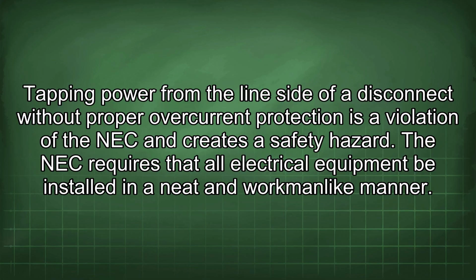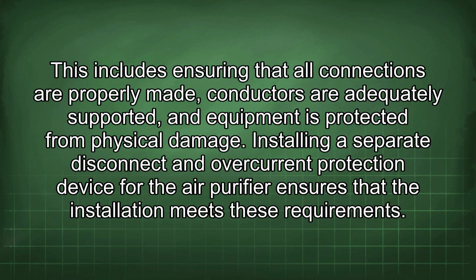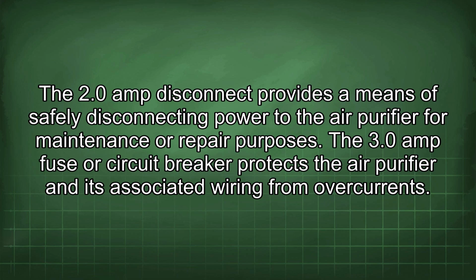The NEC requires that all electrical equipment be installed in a neat and workmanlike manner. This includes ensuring that all connections are properly made, conductors are adequately supported, and equipment is protected from physical damage. Installing a separate disconnect and overcurrent protection device for the air purifier ensures that the installation meets these requirements. The 2.0 amp disconnect provides a means of safely disconnecting power to the air purifier for maintenance or repair purposes. The 3.0 amp fuse or circuit breaker protects the air purifier and its associated wiring from overcurrents.